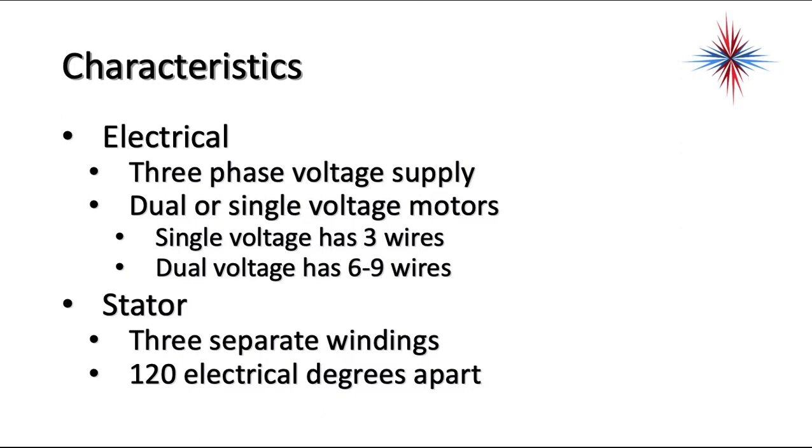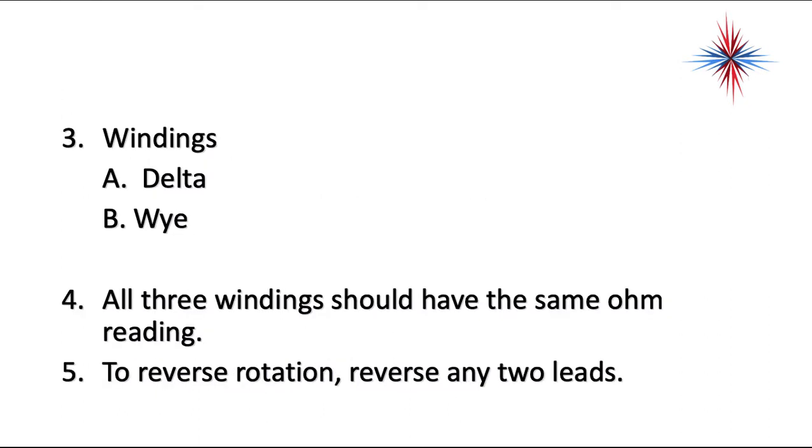So the characteristics is you have a three-phase voltage supply. You have dual or single voltage motors. A single voltage motor has three wires. A dual voltage motor has six to nine wires. The stator is three separate windings. Electrically, they're 120 degrees apart. Three times 120 is the full circle of 360. So the motor windings electrically are exactly 120 degrees apart.